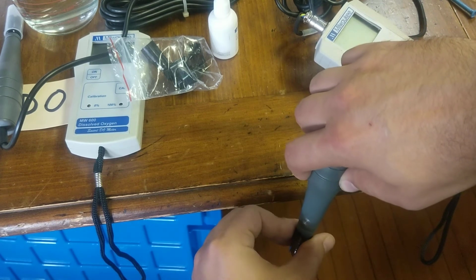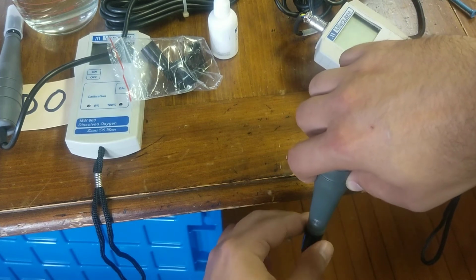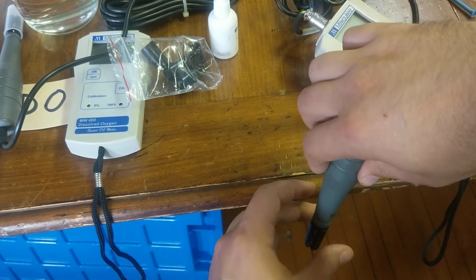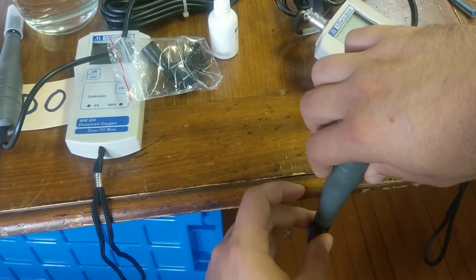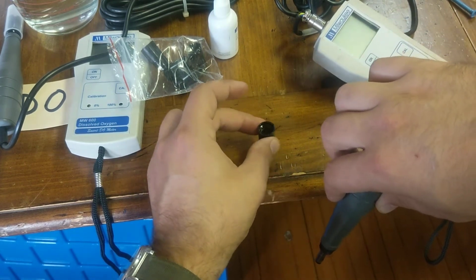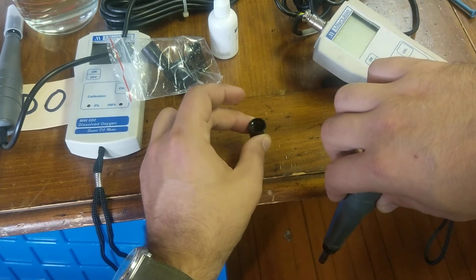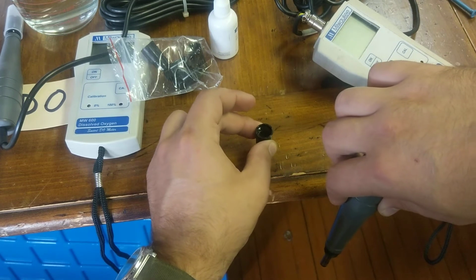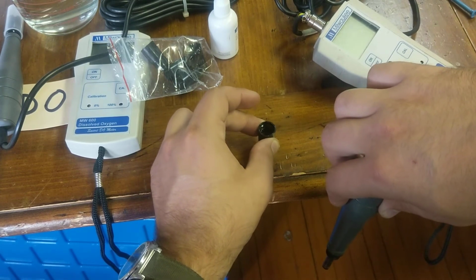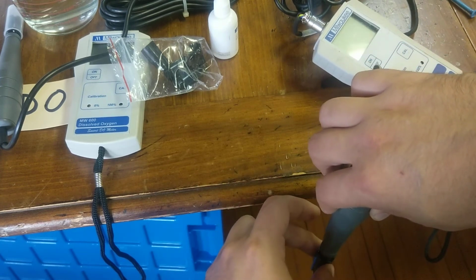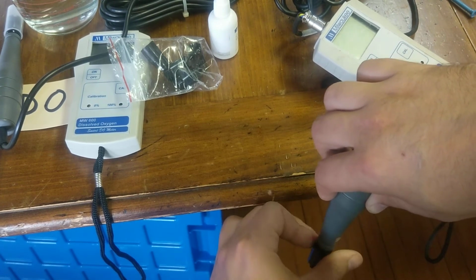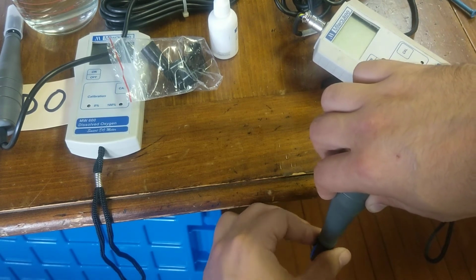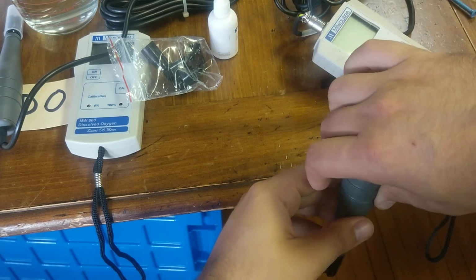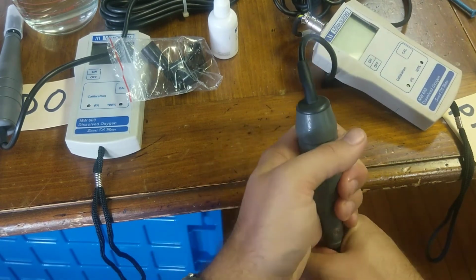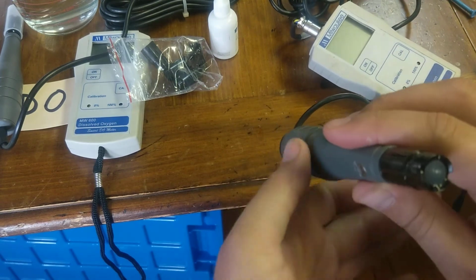That is totally fine. I'm just screwing this probe on as vertical as I can. Now, it helps too, just a second, I forgot to do this, to tap on it just to get the air bubbles out. That'll release some air bubbles off of the bottom. And I find that helps a lot to prevent some more air bubbles from forming on the very bottom of the thing. But you may need to do this 1 or 2 times. And you'll notice some of that fluid leaking out. That's totally fine. I'm just going to tighten it up like that. And then you look on the bottom, and look at that, no bubbles.